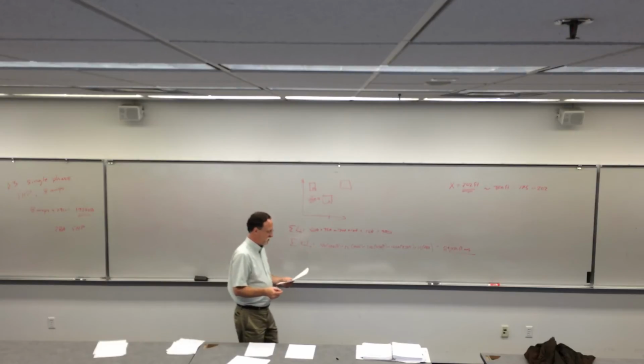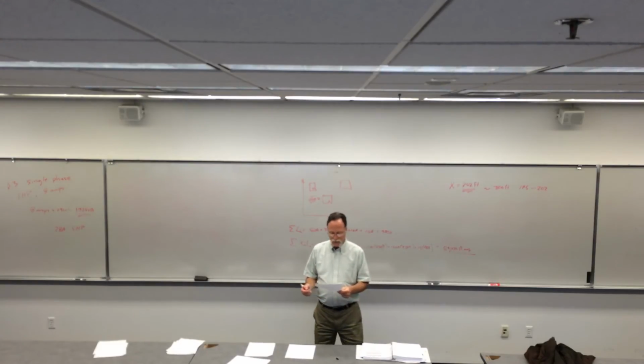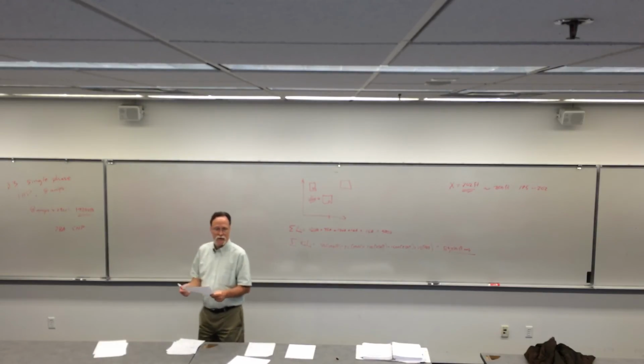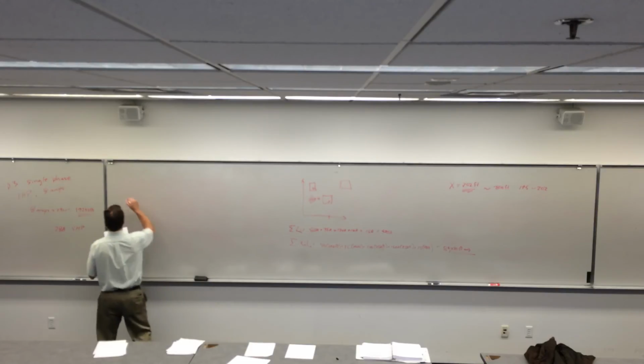Sixty is the minimum standard, and then for the 15 amp load, again, I think the lowest breaker on 240 is 30 amps. So we picked 30 amps on that. Now, problem 6 is where we had a bit of a rub.